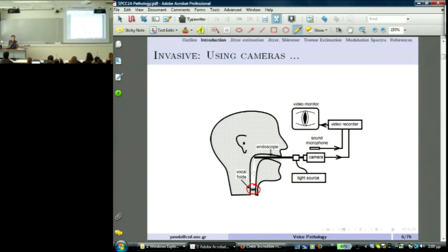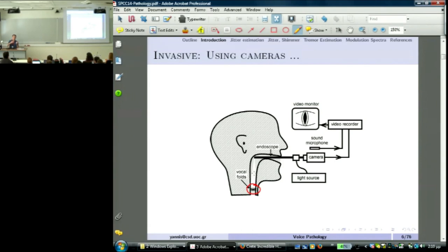If you synchronize the light with the vocal fold vibration frequency — that is, with the F0 — then you see the vocal folds frozen. Of course, voice is not completely harmonic, so there can be F0 estimation errors that make it more difficult to see the vocal folds clearly. Nevertheless, this stroboscopic technique is what we use in the endoscope videoscope.